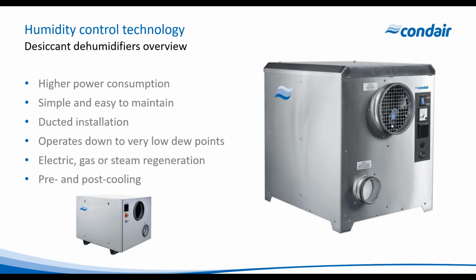And we can use electric, gas or steam for energy for regeneration. So if you've got those available to you, they may be worthwhile considerations. And depending on the set point, we may need pre or post cooling. But typically with these systems, you can get an accuracy of plus minus 2% RH if you've got a stable temperature, plus or minus 0.5 to 1 degree C.